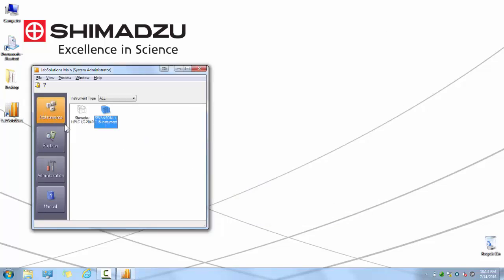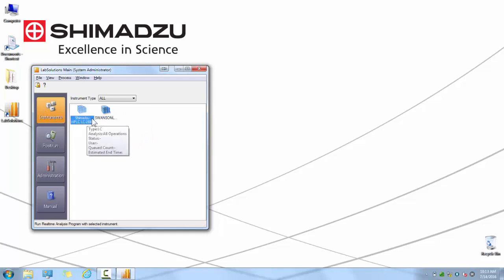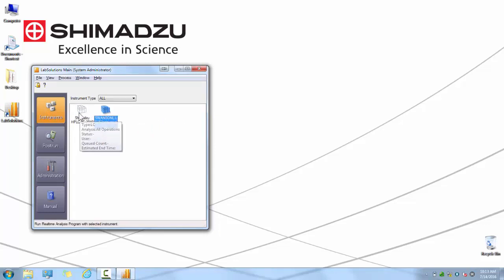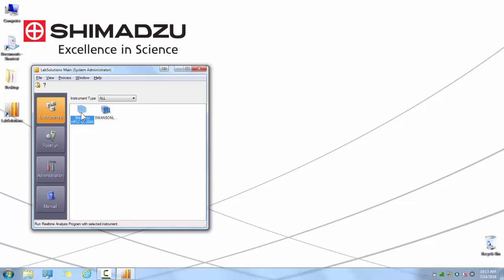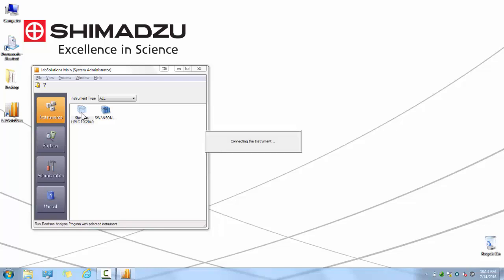Navigate back to the Instruments tab and you should see a new instrument identified with a ghost icon. If you do not, press F5 to refresh the list. To launch the unconfigured instrument, double click on the ghost icon to launch real-time analysis.